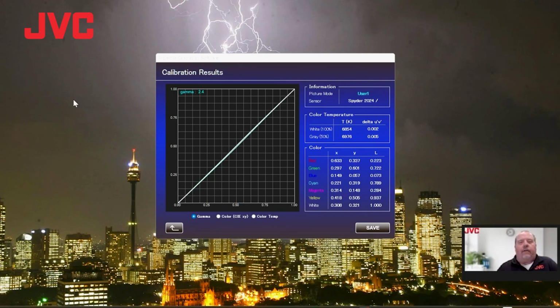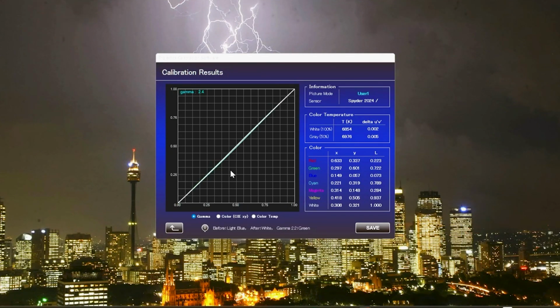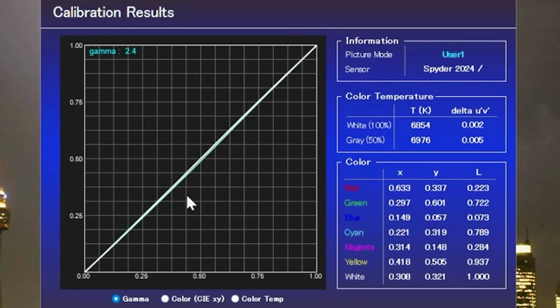So once you're done with the calibration, you'll get the calibration results, and it does a before and after report for you. So you can look at the gamma, the color, and the color temp. If we select the gamma first here, it's really hard to see because this one's been calibrated a bunch of times already.